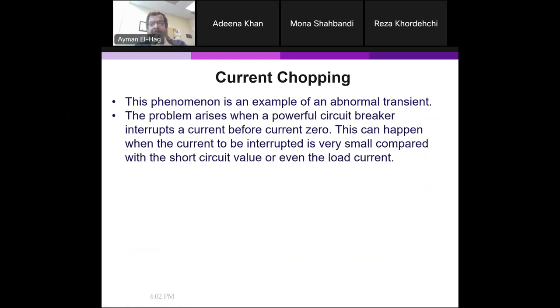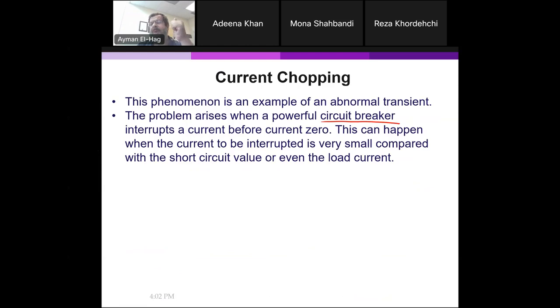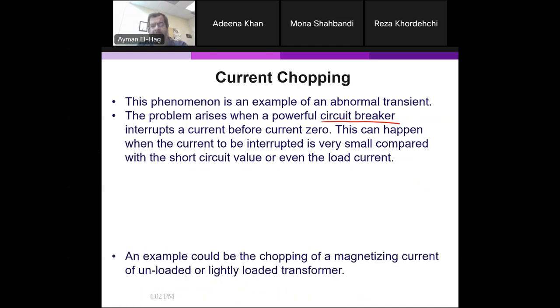This happens when you have a very powerful circuit breaker. The circuit breaker usually interrupts the current at the zero crossing. However, if we have a very small current and a powerful breaker, it might interrupt the current at the peak or at a high value — not at the zero crossing.